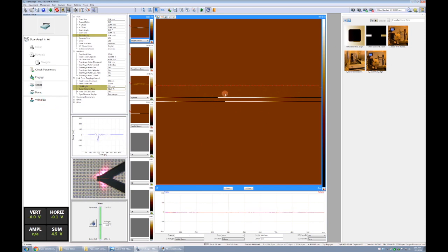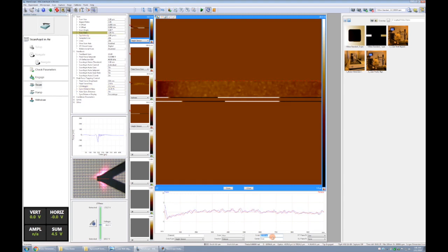All right, so we've landed and we don't see any data yet. So maybe our scale is too large, 300 nanometers. If I put that at 20 nanometers, now we can see some topography as we're scanning the silicon oxide texture of the sample. But we might be between two of these boxes, and we want to ultimately image one of these etched boxes. So we need to figure out how to do that.